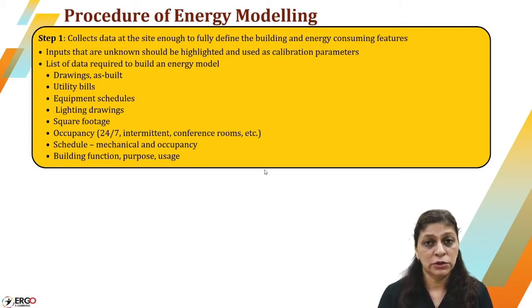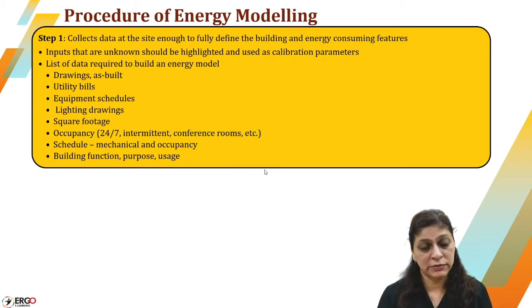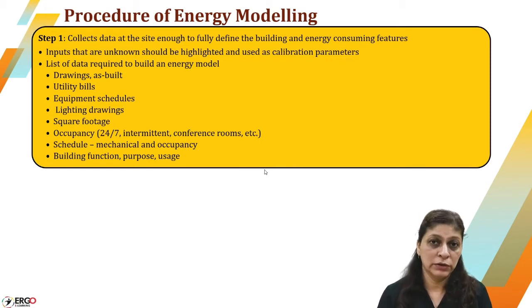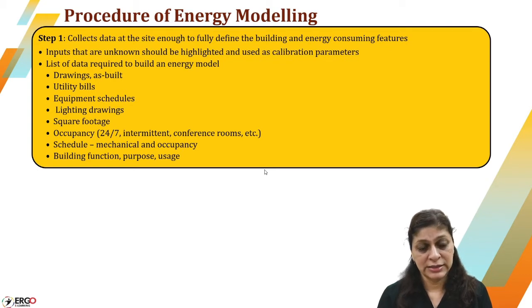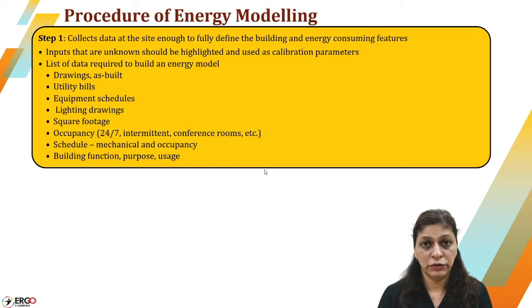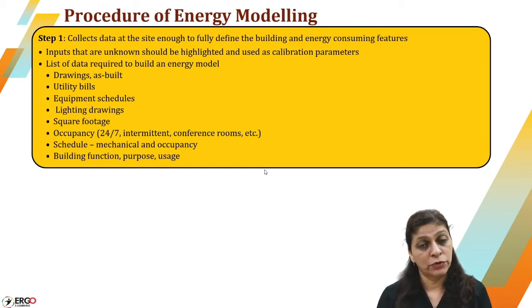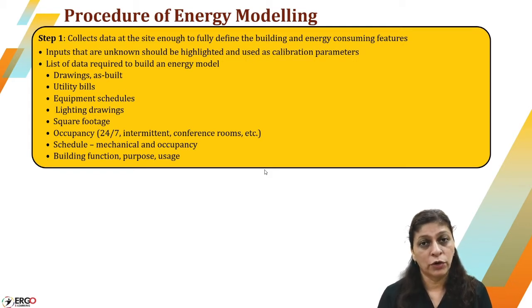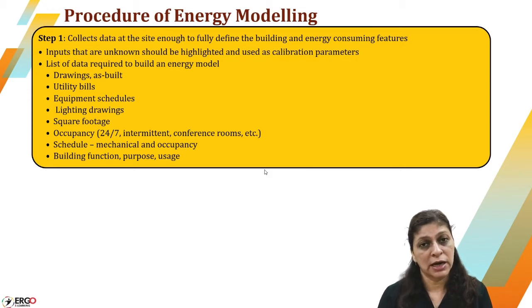Data gathering starts with drawings of the actually built building, utility bills of electricity as well as gas, then equipment schedule — when and in which pattern they are going to operate — lighting drawings and lighting density details, the square footage information of each part of the building, what is the occupancy of the building, type of occupancy, nature of use, schedule of occupancy, and building functions as well as purpose.